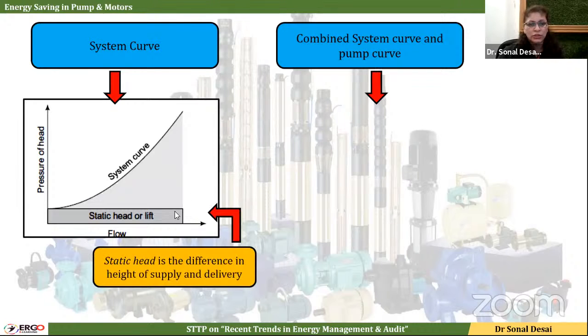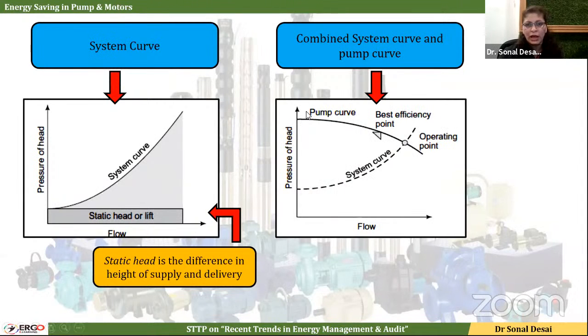This system curve shows two types of head. One is static head, that is how much height the fluid is being lifted, and then dynamic head, that is the friction taken care of by a pump. So when we overlap the pump curve and system curve, it will be like this. Their intersection point depicts the operating point, the advisable operating point, or the best operating point.